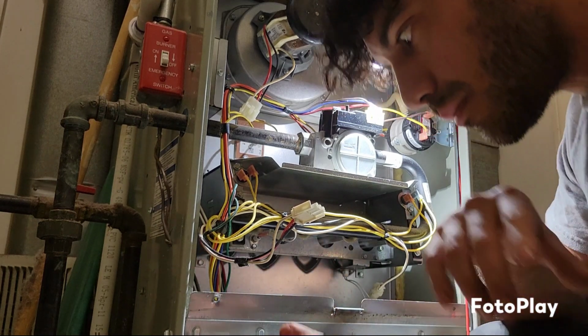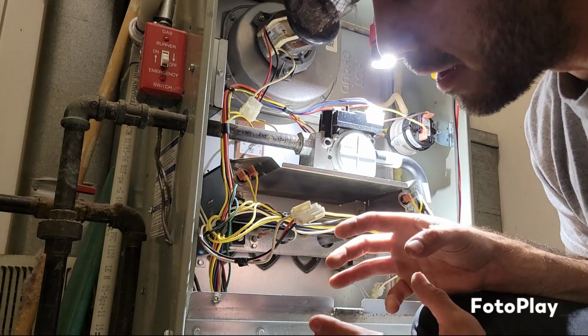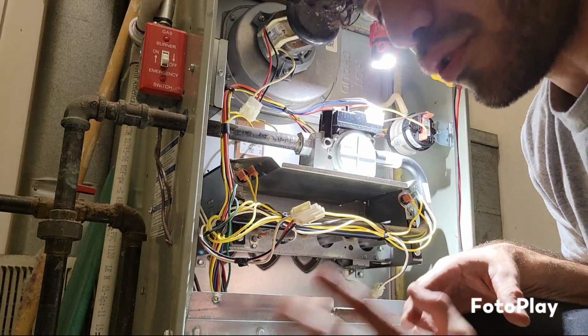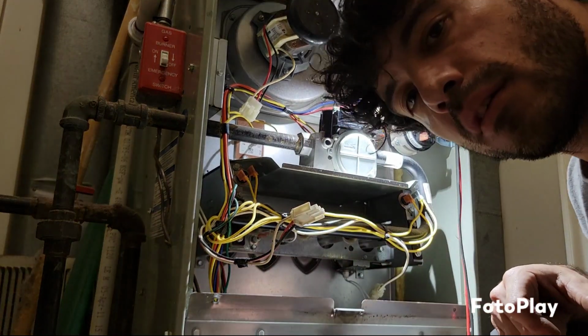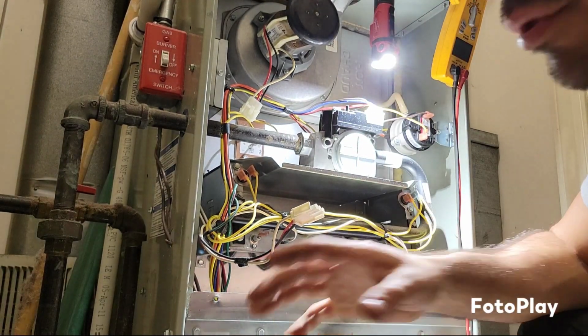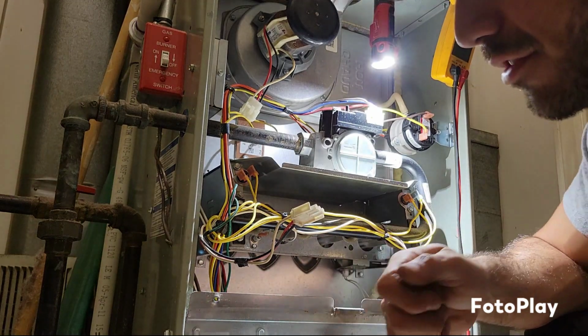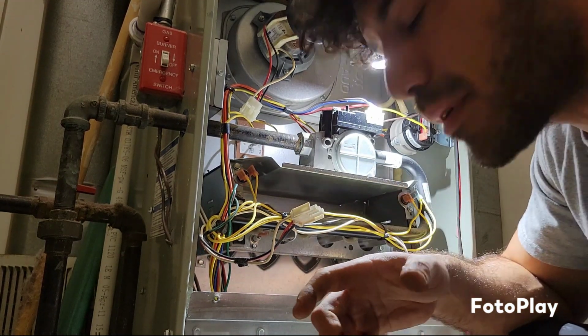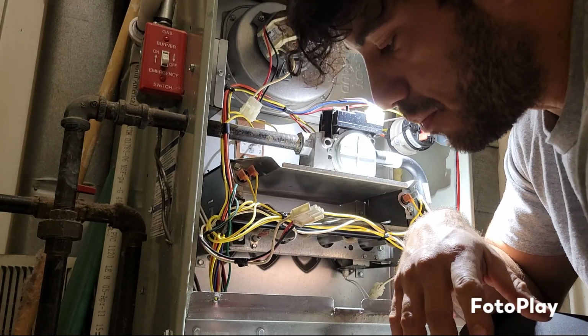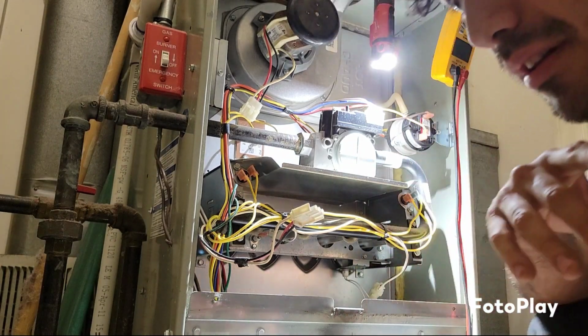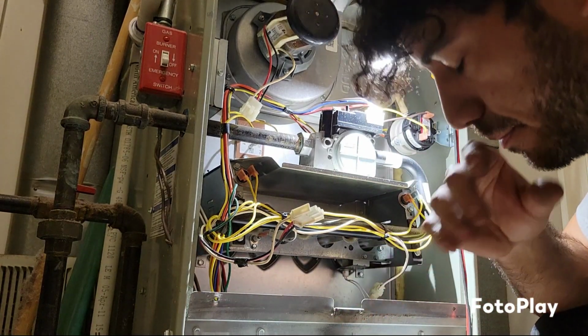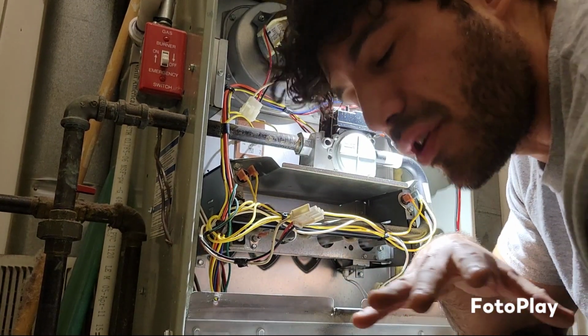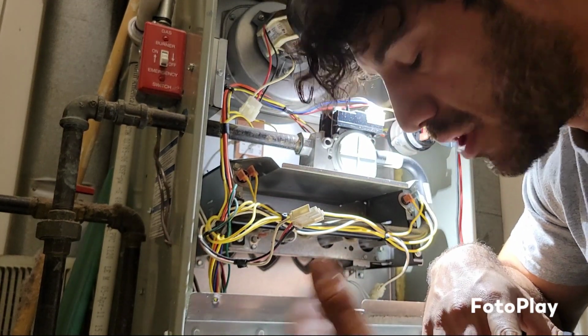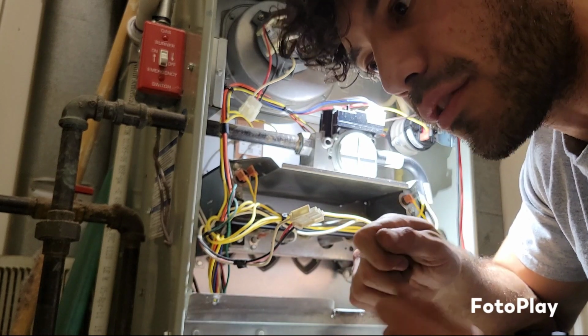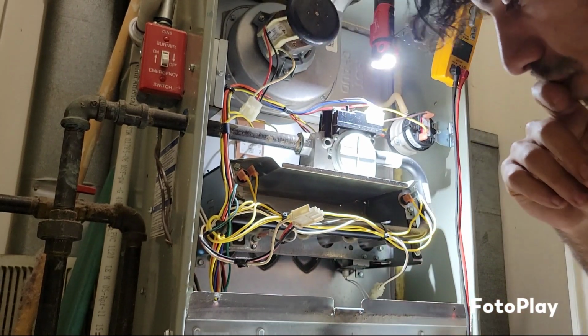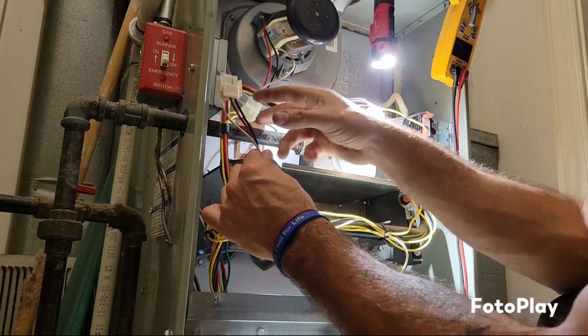Now, because of this particular board and this particular setup, you also want to make sure your polarity is correct. So you want to make sure that you go to ground on each leg and there's no voltage on the neutral side and nothing like that, because that can cause this particular board in this scenario to have issues, right? So anyway, we established that we don't have a polarity issue when I was originally here. So we checked everything to ground, made sure everything was good. So we're back here to square one.